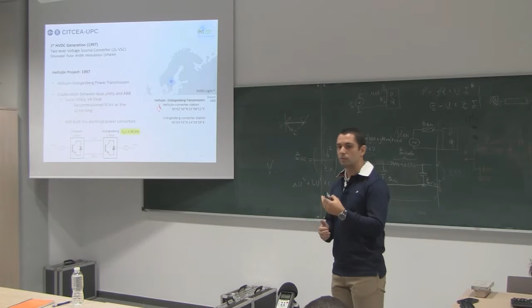Are you familiar with this type of converter? This is a 2-level converter. Basically it can only produce 2 voltage levels, plus VDC or minus VDC at the AC output, as Carlos mentioned. You emulate an AC voltage waveform using PWM, modulating the AC voltage at the output. Another detail is that nowadays IGBTs are up to about 6 kV each. So in order to reach higher voltage on the DC side, it's not just one IGBT - it's a series connection of IGBTs. Instead of having one, you have hundreds sometimes.